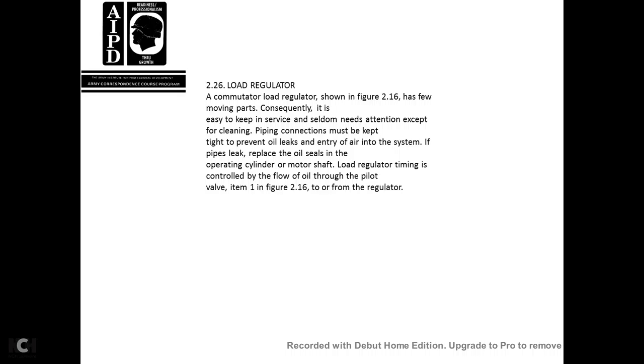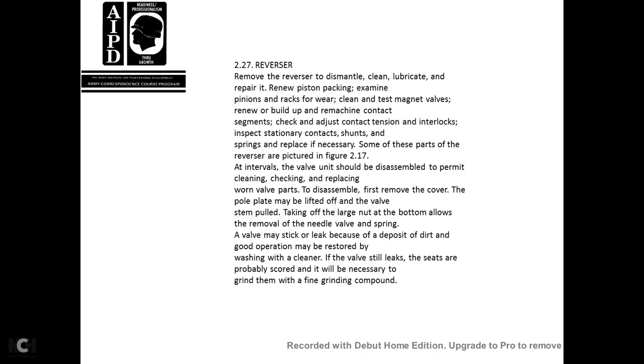226, the commutator load regulator shown in figure 216 has few moving parts. Consequently, it is easy to keep in service. It seldom needs attention except for cleaning. Pipe connections must be kept tight to prevent oil leaks and air entry into the air system. If the pipes leak, replace the oil seals in the operating cylinder or motor shaft. Load regulator timing is controlled by the flow of oil through the pilot valve, item 1 in figure 216, to and from the regulator.